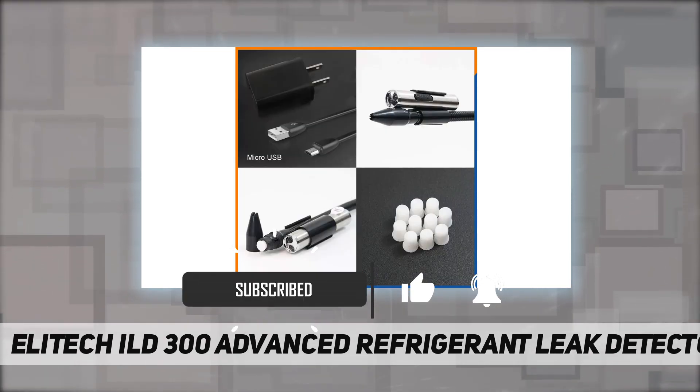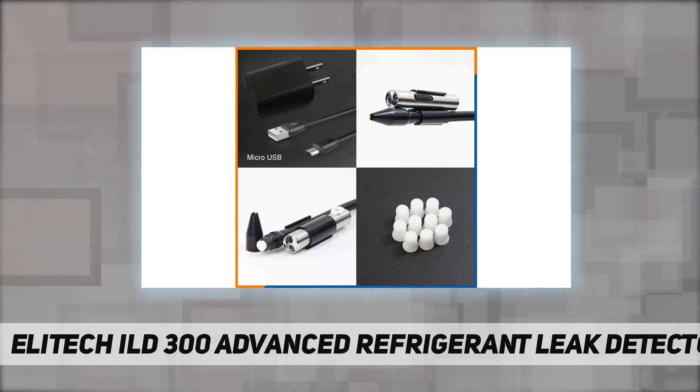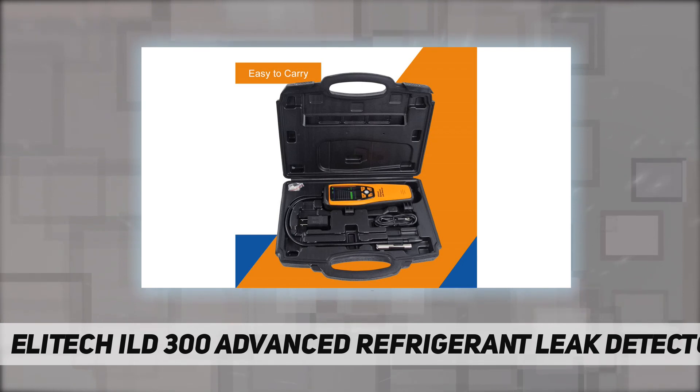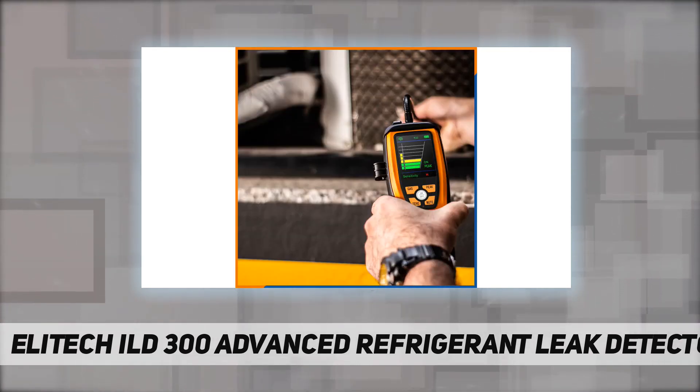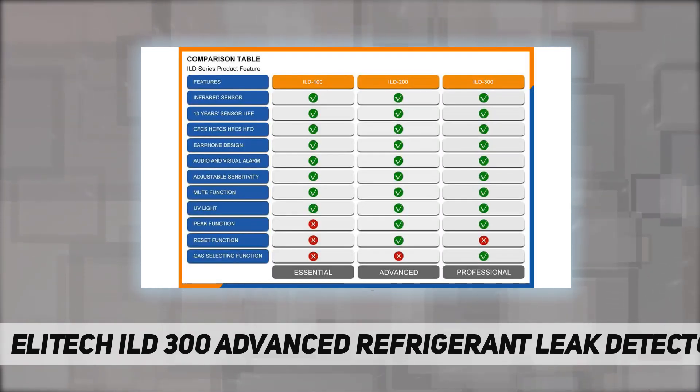It performs on all halogenated refrigerants, outperforming traditional corona and heated diode sensors. There are three sensitivity levels — high, medium, and low — with a maximum sensitivity up to 0.14 ounces per year. The refrigerant selectable gas button allows you to select the corresponding refrigerant.